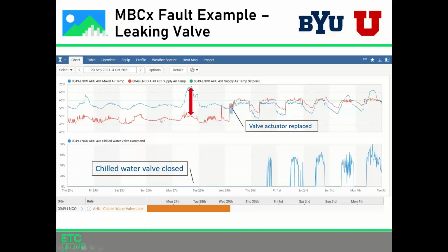You can see that the supply temperature in this first half of the graph is not meeting its set point at all. And its chilled water valve is closed, but somehow we're seeing this big temperature drop from this mixed air to the supply. So this is where we can see a fault being flagged by the software. This little orange block represents the fault that's being detected.